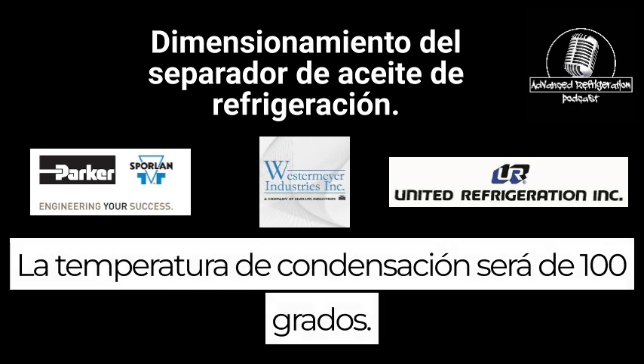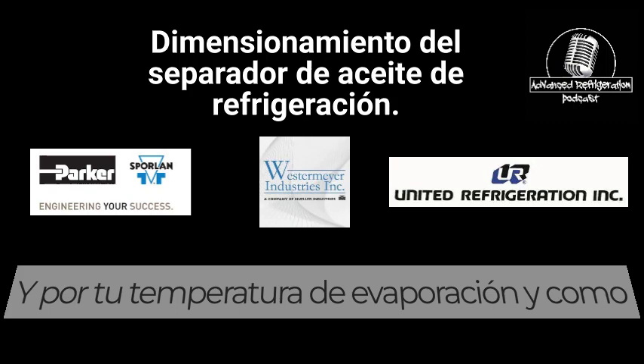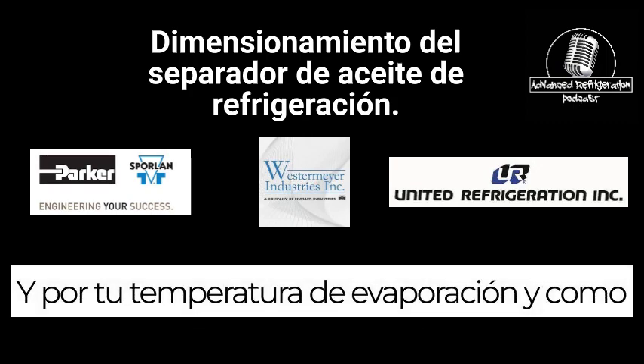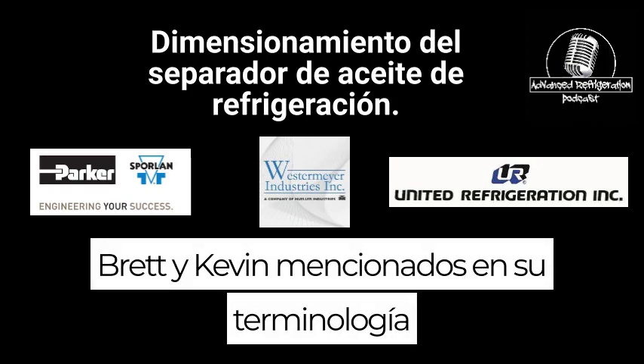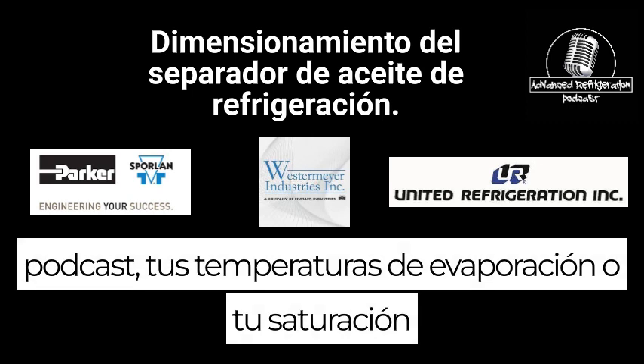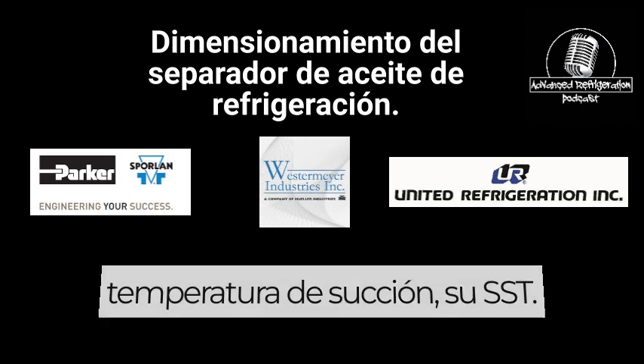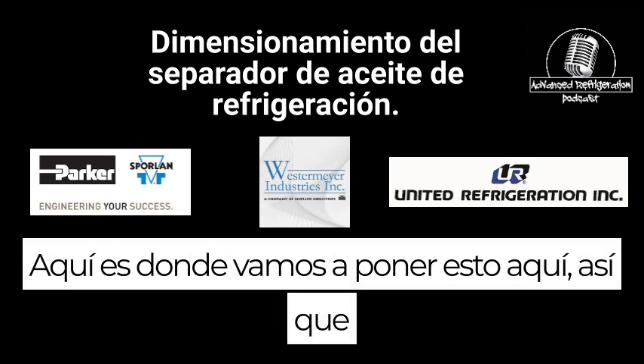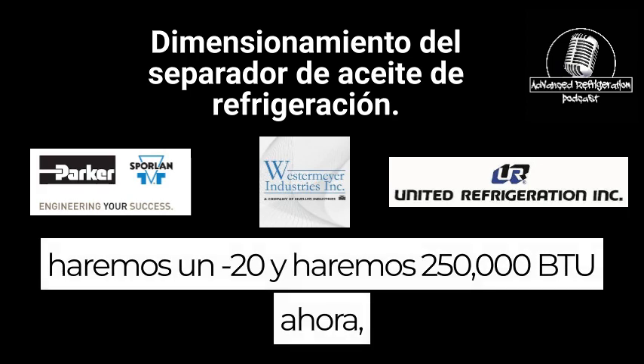Condensing temperature, we'll do 100 degrees. And for your evaporating temperature, like Brett and Kevin mentioned in their terminology podcast, your evaporating temperature, or your saturated suction temperature, your SST, is where we're going to put this here. So we'll do minus 20 and we'll do 250,000 BTUs.